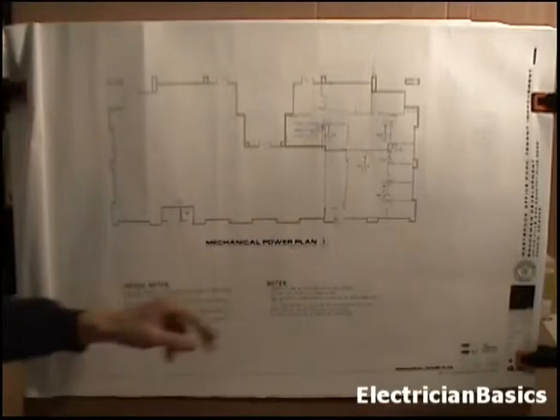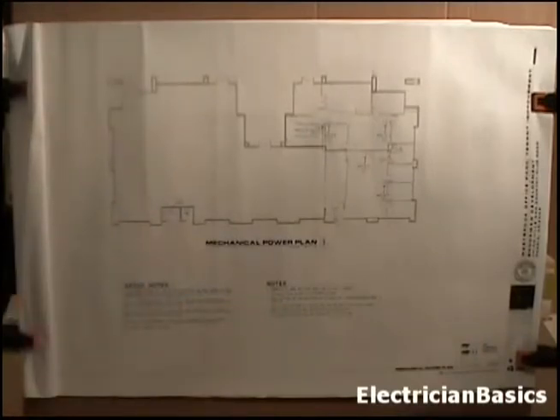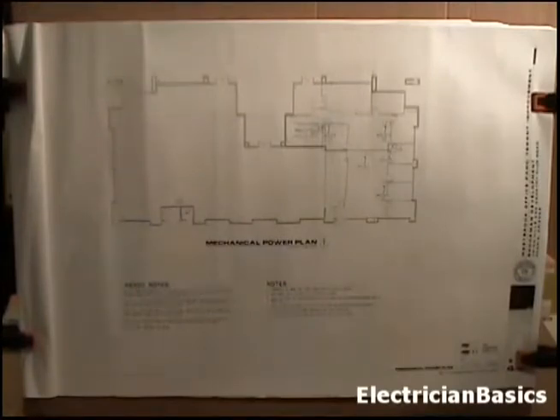The next page of this lesson is sheet E 4.2, Mechanical Power Plan. Now the scale on this sheet is 1/8 of an inch equals 1 foot. And of course we should read the keyed notes and the notes every time. Let's look right here. We have keyed note 5 and it says existing 1200 amp, 120/208 volt 3-phase 4-wire SES. In other words, this is where the electrical feed from the utility company comes in.